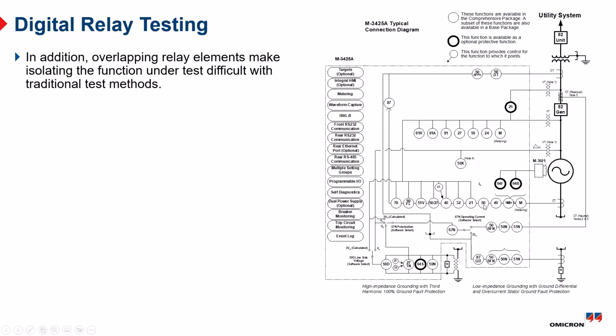So for the 50, we have 3 different phases and sometimes multiple levels of 50 element that you can set, and so forth. So you can see this particular relay has, I don't know, 20-something functions, but as far as the total protective functions, probably approaching 100 different functions. And they're all mapped to different voltage and current inputs on the relay. So testing has gotten a bit more complex as far as testing a multifunction relay.